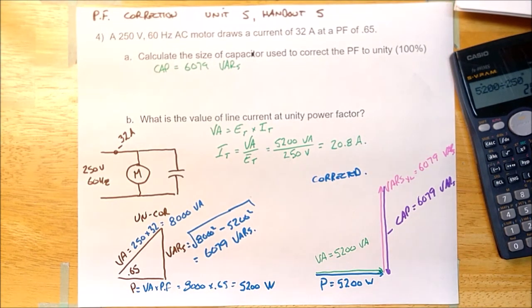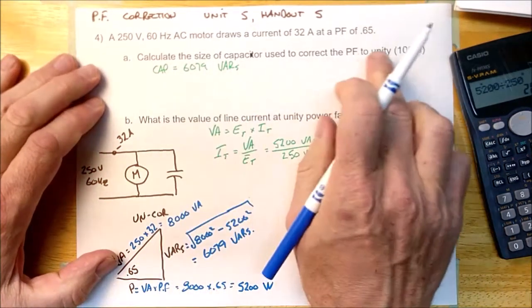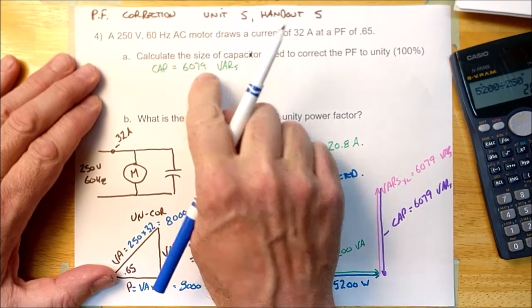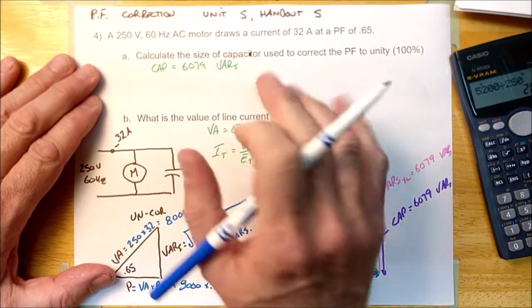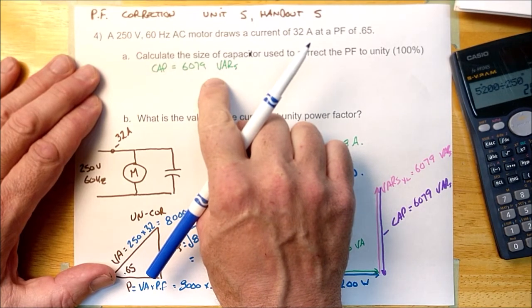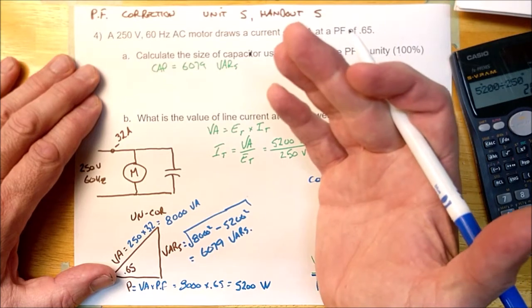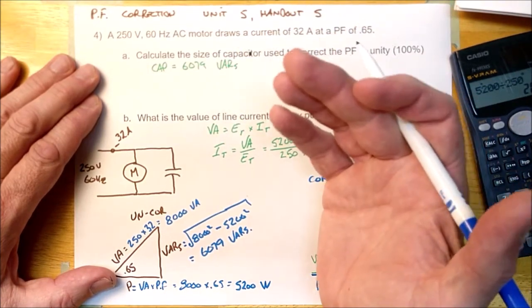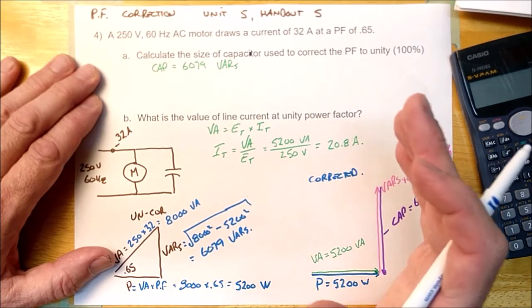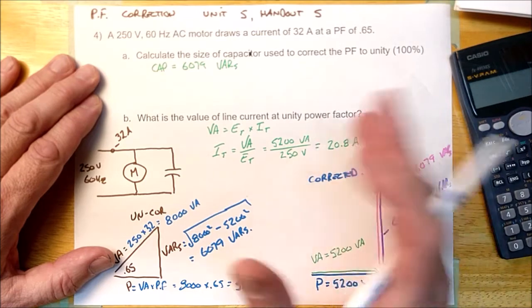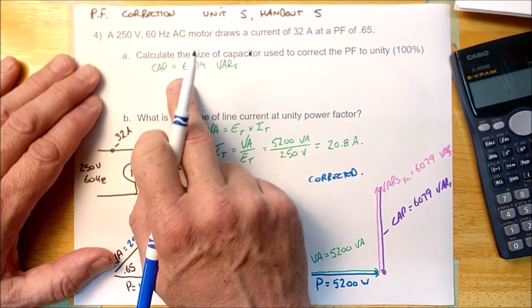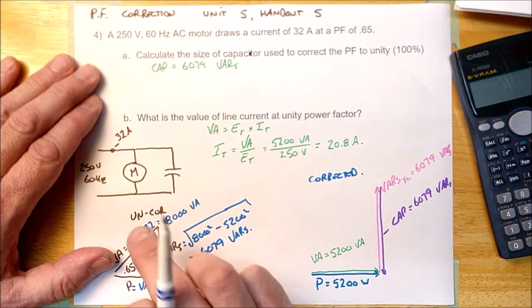Now there's one more thing I want to show you because some of the homework questions are going to ask you how many microfarads this capacitor is. So it's going to ask you to calculate the capacitor in VARs. And by the way, power factor correction capacitors are sold to you in VARs. We're going to calculate how many microfarads it is. But understand that when you order a power factor correction capacitor, you're going to order in VARs or KVARs. It's just like baseboard heaters. When you go and order a baseboard heater, you're not going to ask for a certain amount of ohms. What you're going to ask for is how much power. Same with caps. You're going to order them in VARs or KVARs. This is going to be a 6KVAR capacitor that you need to correct this motor.